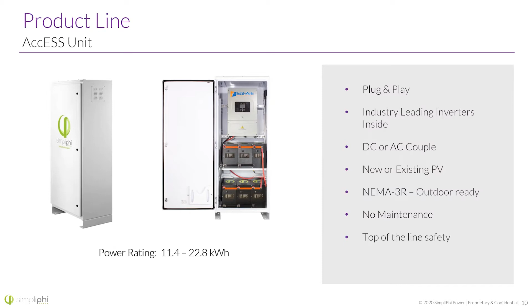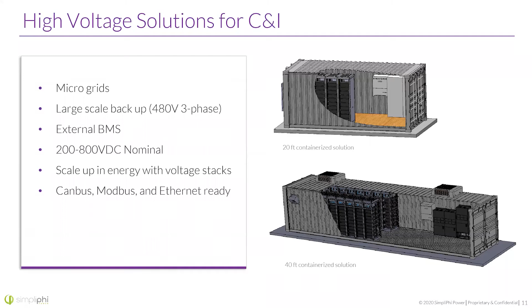Okay, last 2, and then we'll get to the kind of bulk of the presentation regarding the topic. High voltage solutions are for C&I projects, mostly commercial and industrial stuff. Microgrids are a great example of what I see these used for, as well as large-scale backup, so maybe you have 480-volt 3-phase on the AC side and you need a large inverter. This would typically pair with those inverters. This battery can be scaled from 200 to 800 VDC nominal on the stacks, and then those stacks can be paralleled to build up total energy storage capacity. The BMS is an external BMS, has CAN bus, Modbus, and Ethernet connections ready to go, and it actually has its own monitoring platform built directly into the battery. And very last, we have...